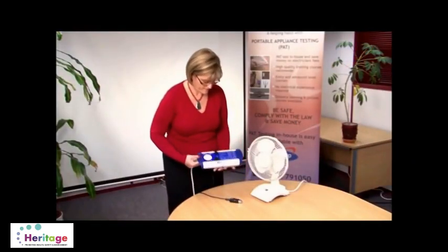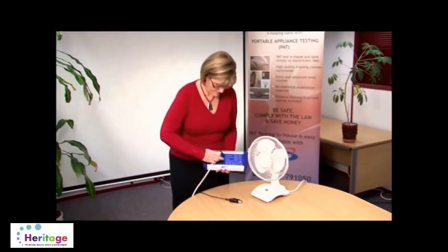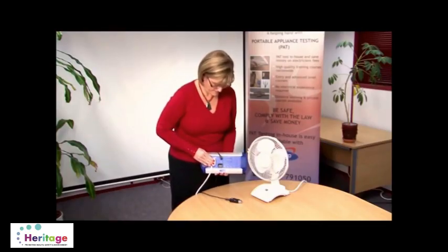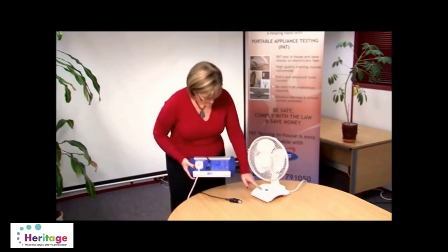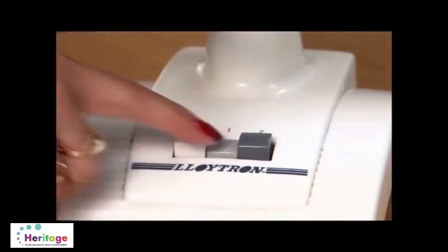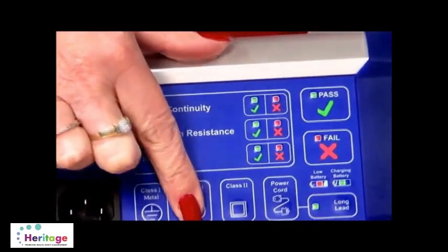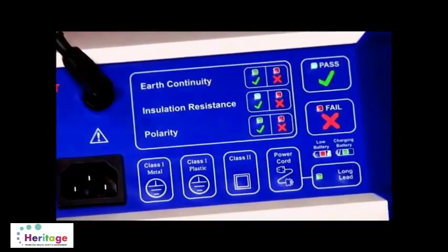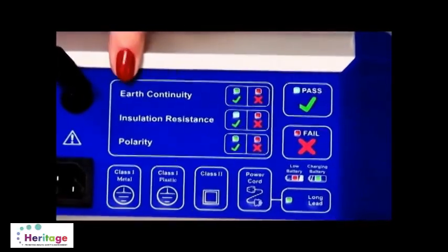Testing a Class 1 plastic appliance. Plug the appliance into the BAT-PAT. On these appliances, there is no place to clip the earth lead onto, so leave this to one side. Make sure that the appliance is switched on. Press the Class 1 plastic button and wait for the BAT-PAT to display the results of the insulation resistance test.